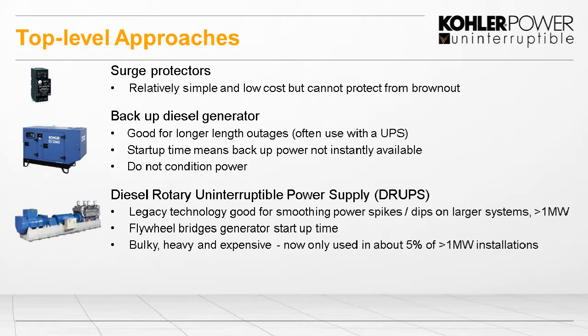Another top level approach is the diesel rotary UPS, often called DRUPs. And these are an older technology, and these are typically used on large power systems greater than a megawatt. But they've been declining, and they're only about 5% of the installations at that size that use the DRUPs. And these are flywheel sets that bridge the generator startup time. And these are bulky, heavy, and relatively expensive.